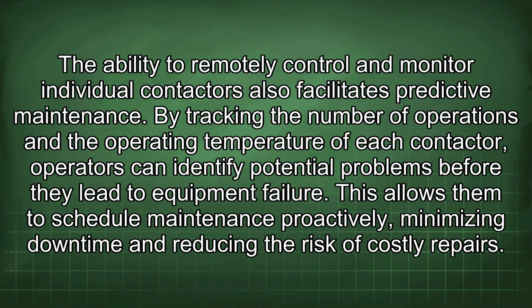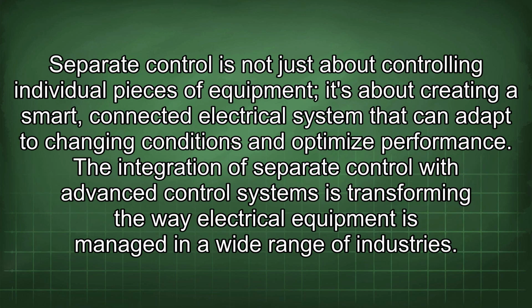The ability to remotely control and monitor individual contactors also facilitates predictive maintenance. By tracking the number of operations and the operating temperature of each contactor, operators can identify potential problems before they lead to equipment failure. This allows them to schedule maintenance proactively, minimizing downtime and reducing the risk of costly repairs. Separate control is not just about controlling individual pieces of equipment, it's about creating a smart, connected electrical system that can adapt to changing conditions and optimize performance.